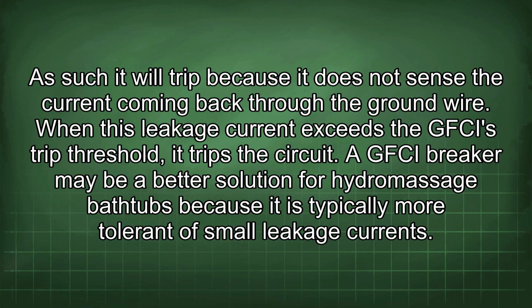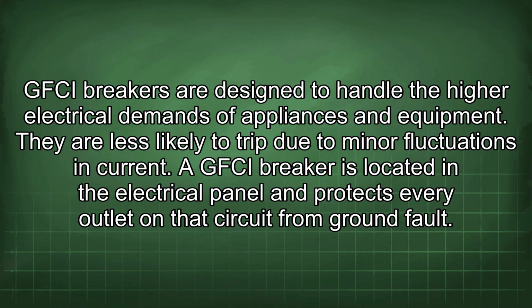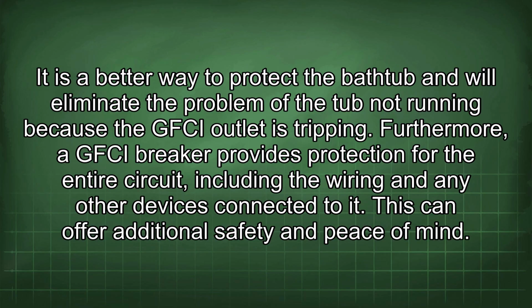A GFCI breaker may be a better solution for hydromassage bathtubs because it is typically more tolerant of small leakage currents. GFCI breakers are designed to handle the higher electrical demands of appliances and equipment. They are less likely to trip due to minor fluctuations in current. A GFCI breaker is located in the electrical panel and protects every outlet on that circuit from ground fault. It is a better way to protect the bathtub and will eliminate the problem of the tub not running because the GFCI outlet is tripping. Furthermore, a GFCI breaker provides protection for the entire circuit, including the wiring and any other devices connected to it. This can offer additional safety and peace of mind.